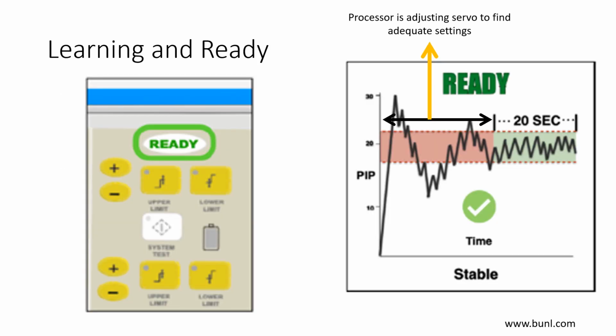The jet ventilator provides numerous indicators that provide helpful information about the ventilator's operations. The ready button will light up to indicate that the alarms have been calculated, set, and active. When the ready button is not illuminated, the jet ventilator is considered non-ready, meaning the alarms are not active. The ventilator will enter non-ready mode by pressing Enter or Standby. When the ventilator is non-ready, the patient should not be touched because the ventilator is in a learning mode.